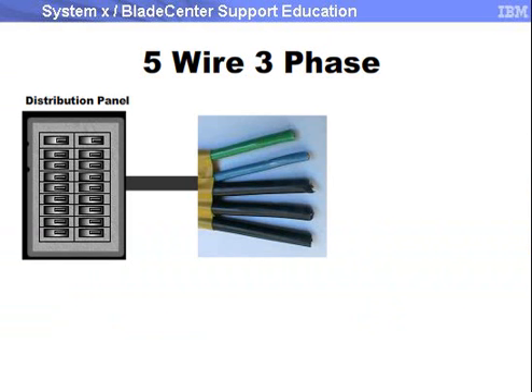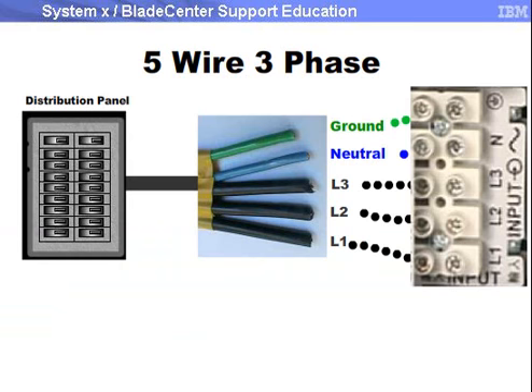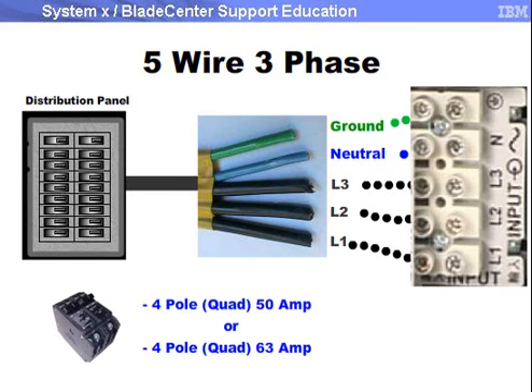5-wire three-phase wiring connects the L1, L2, L3, neutral and ground wires from the distribution panel to the input terminal block of the UPS. The external circuit breaker in the distribution panel will typically be a 4-pole 50 amp or a 4-pole 63 amp breaker, depending on the UPS output rating and the local electrical codes in force.